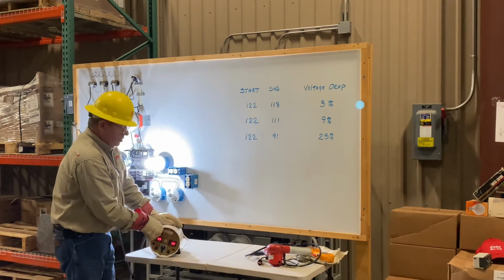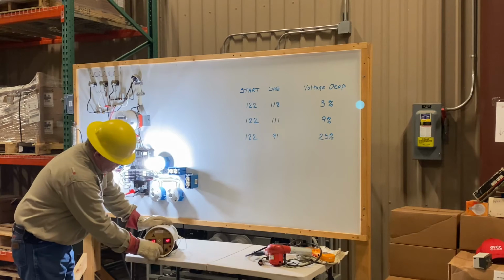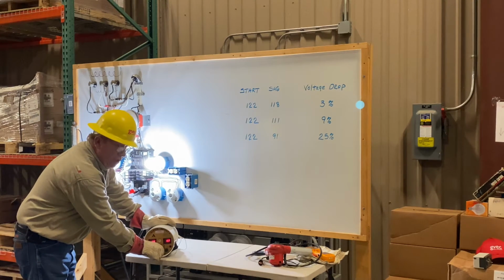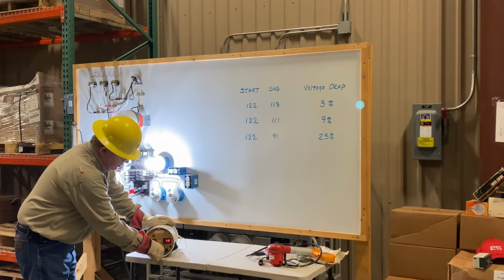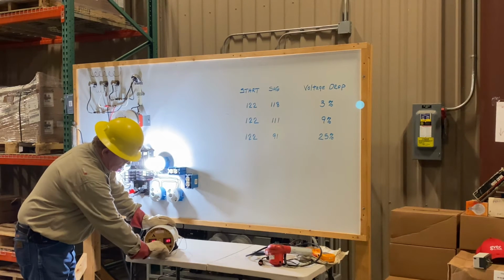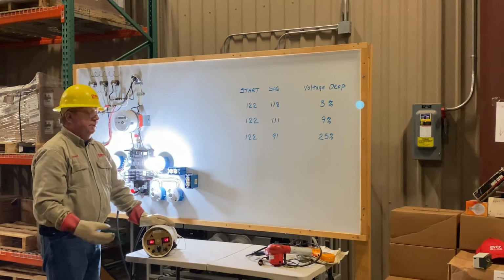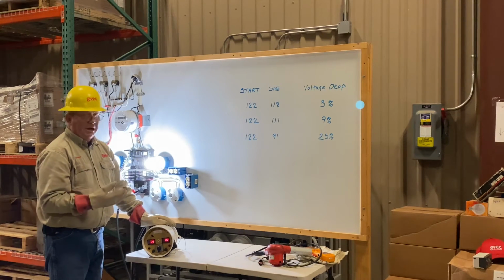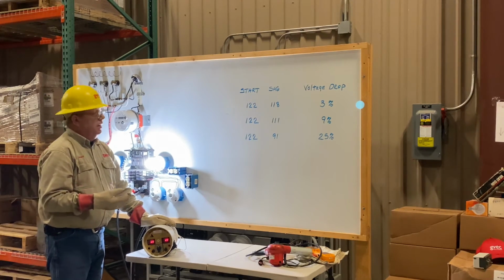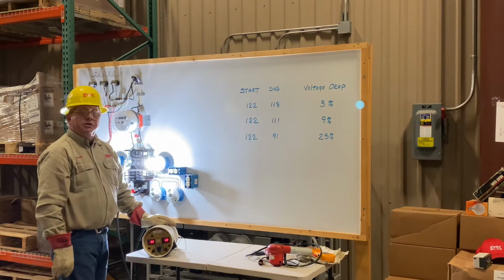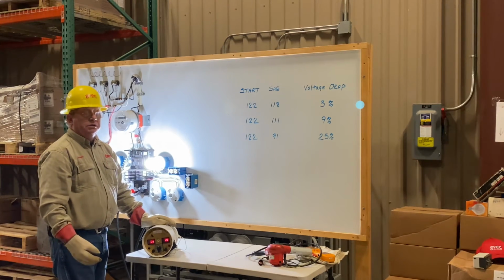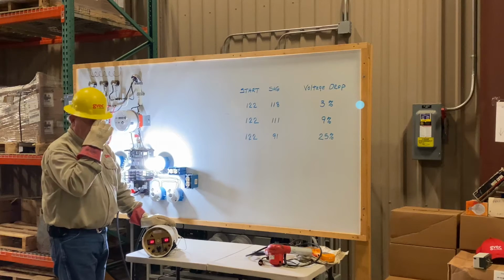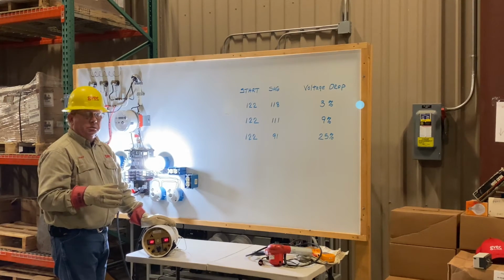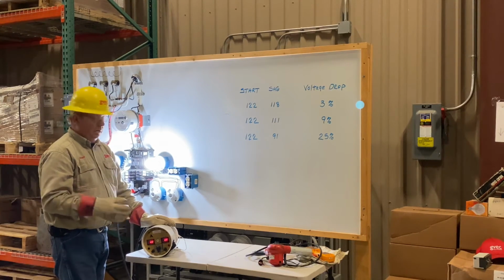We're going to load. You should be able to see those bulbs as this is with a good neutral. That's the voltage drop that the bulb sees in normal times. Air conditioning compressor comes on, it falls to 111. 111 is a 9% voltage drop. And if they have a large air conditioner, that's not uncommon. We see it often. But that is not a neutral problem. It's a voltage drop problem.